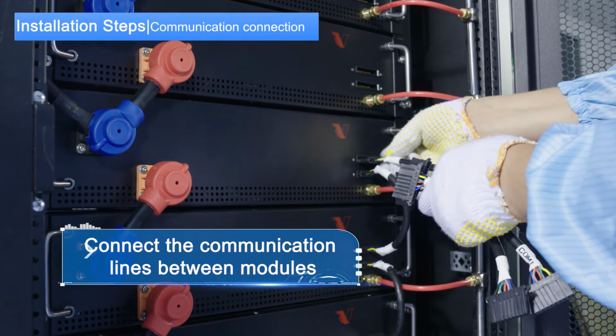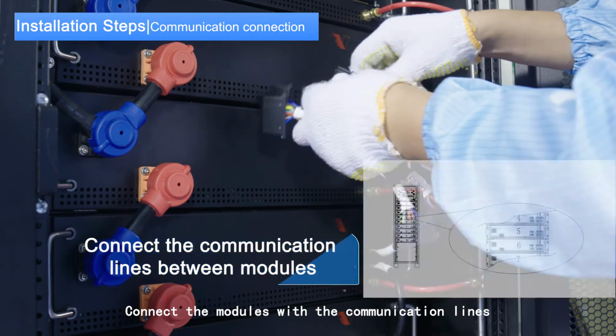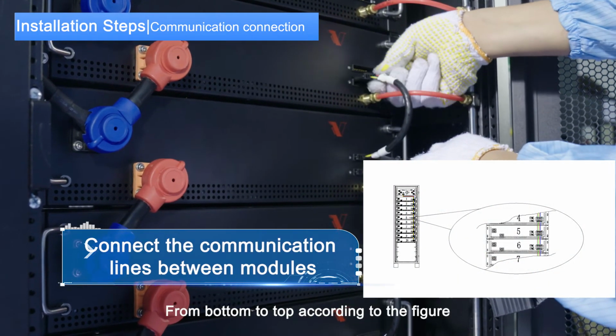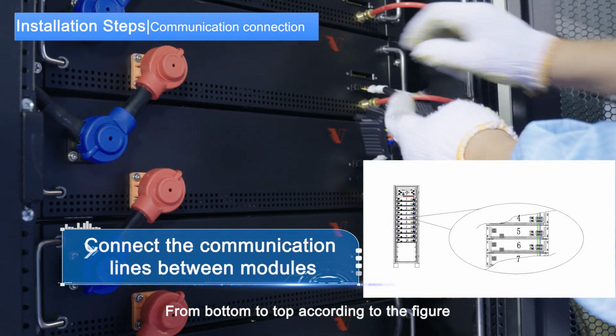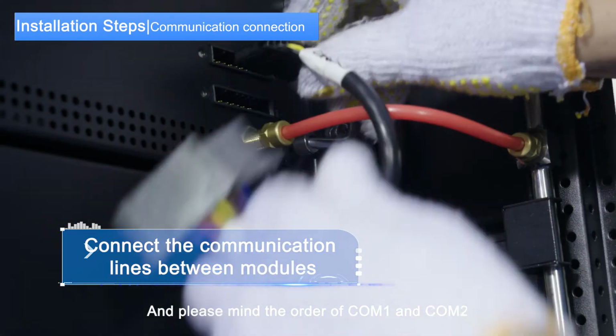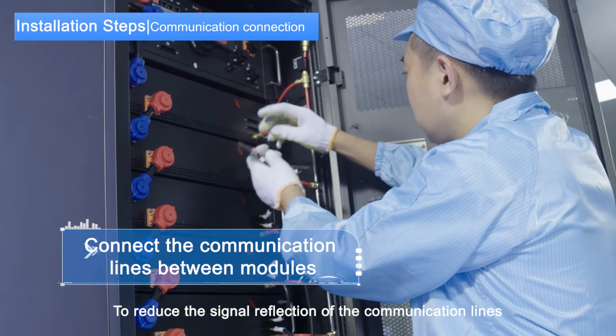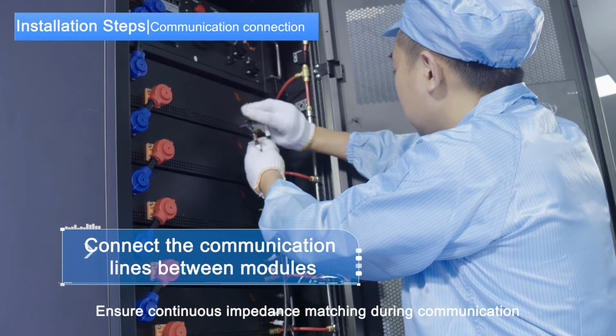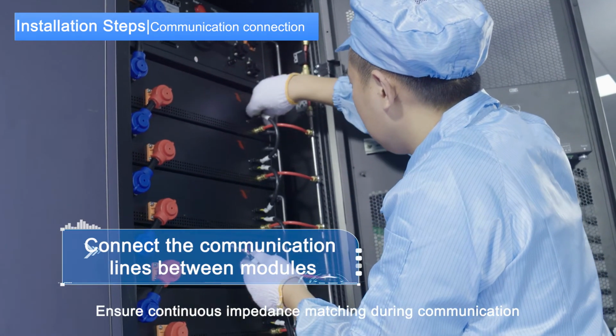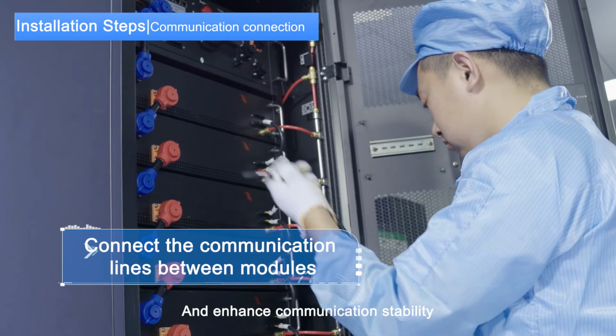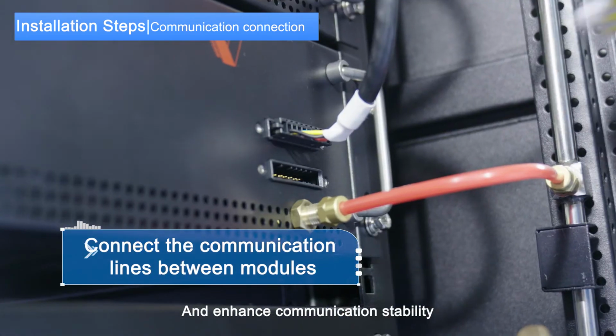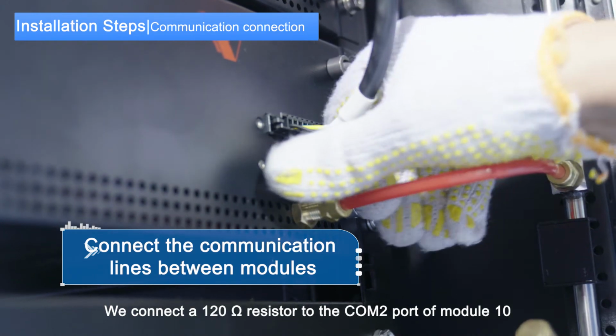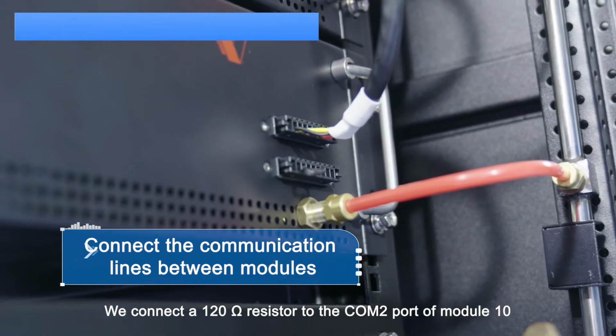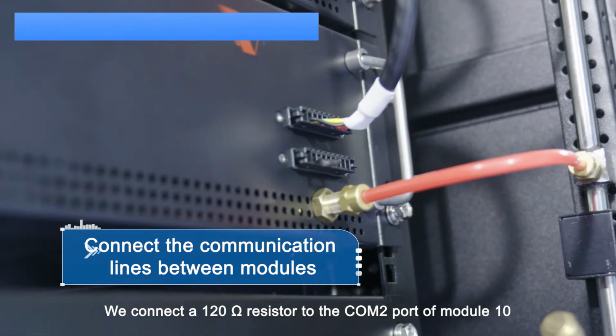Connect the communication lines between modules. Connect the communication lines between modules from bottom to top according to the figure, and please mind the order of COM1 and COM2 to reduce the signal reflection of the communication lines. Ensure continuous impedance matching during communication and enhance communication stability. We connect a 120 ohms resistor to the COM2 port of module 10.